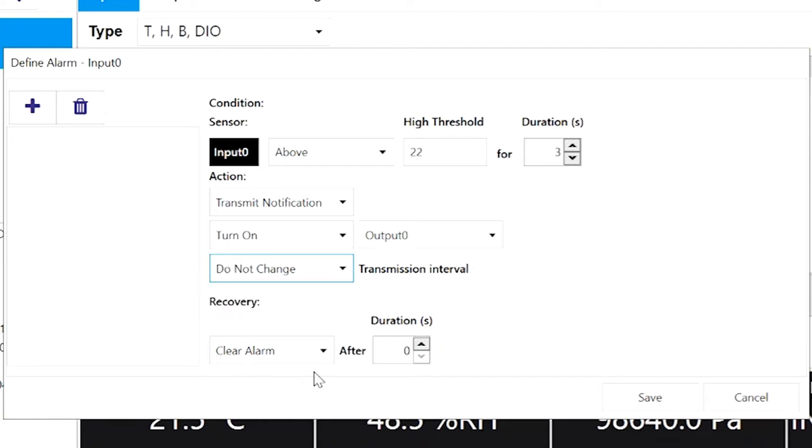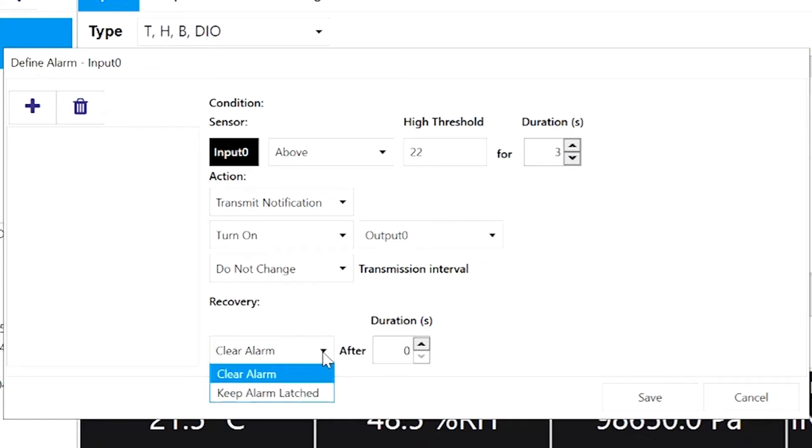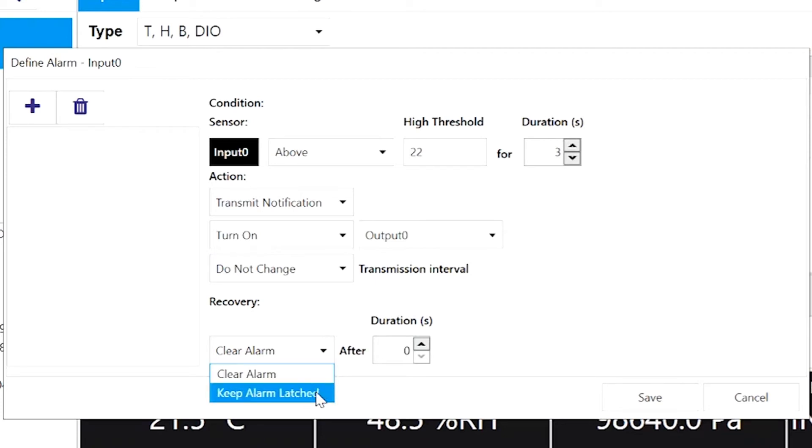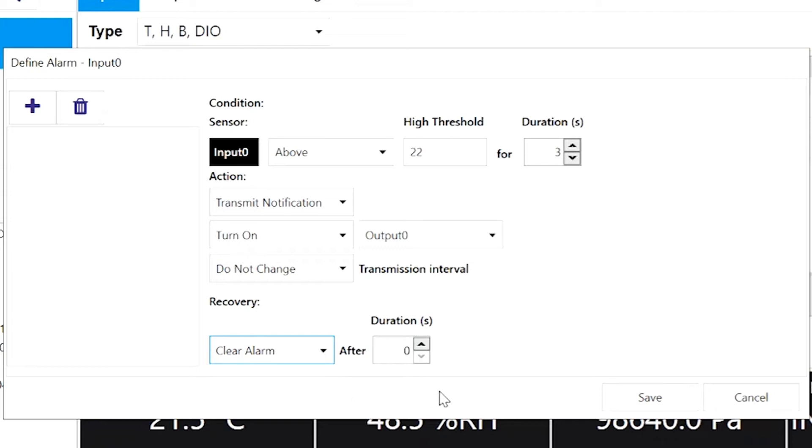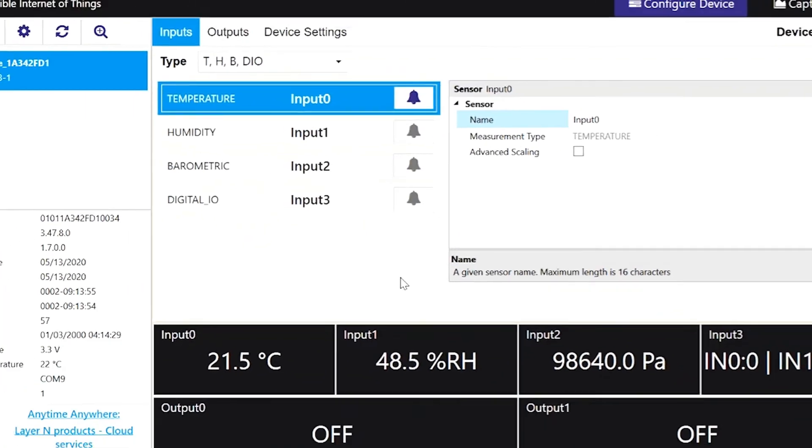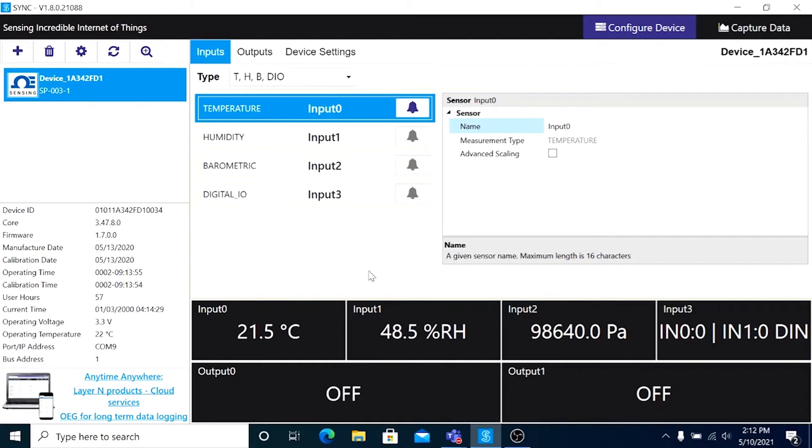And under Recovery, you can tell Sync what to do once the alarm state has passed. In the drop-down, choose Clear Alarm if you want it to just go away. Or Latch Alarm if you want someone to perform a manual operation to clear the alarm. And Duration tells the system how long you want the alarm condition to be over before the alarm is cleared. I'll set it to two seconds before it clears the alarm.